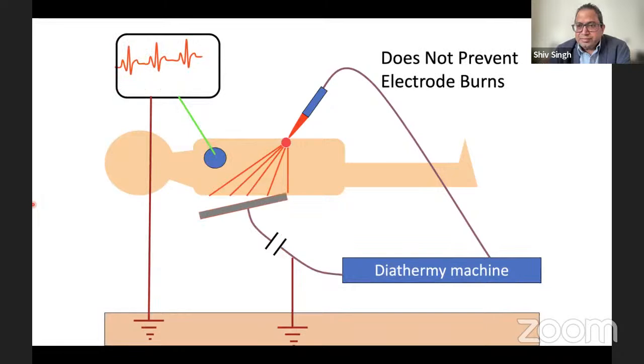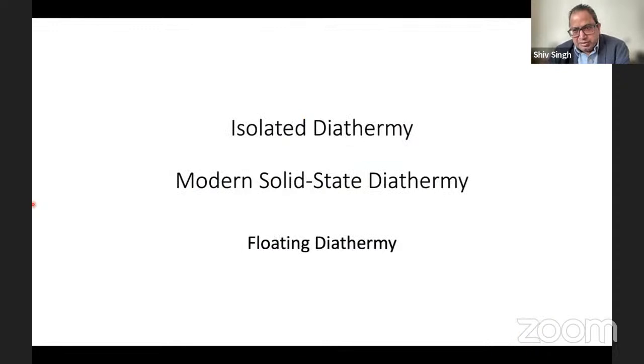The current could still flow through the electrodes, complete a circuit through the earthing, and cause electrode burns. So this did not prevent electrode burns in this patient. It prevented the burns from the diathermy, it prevented microshock, but it did not prevent the electrode burns. Then came the modern diathermy, which is solid state diathermy, which uses a floating circuit or isolated circuit.